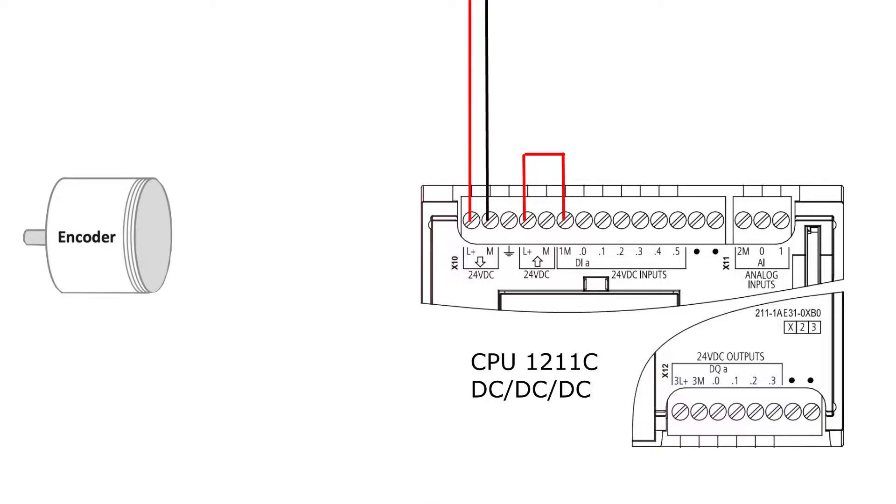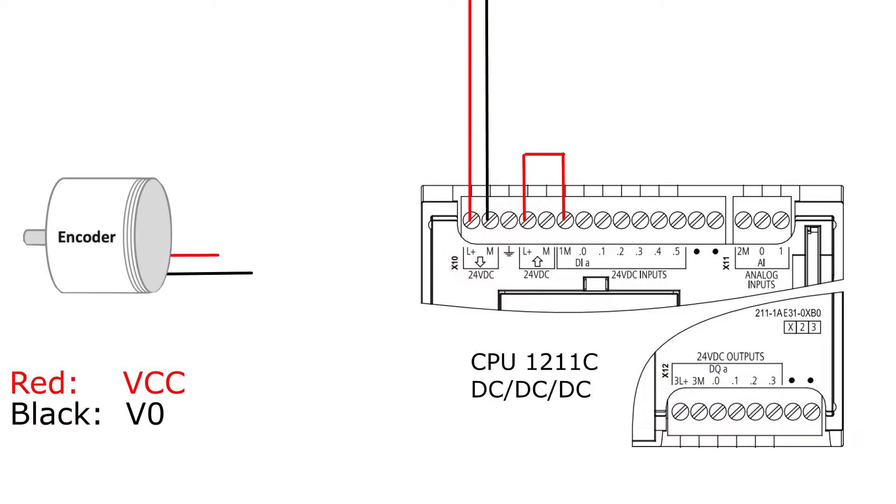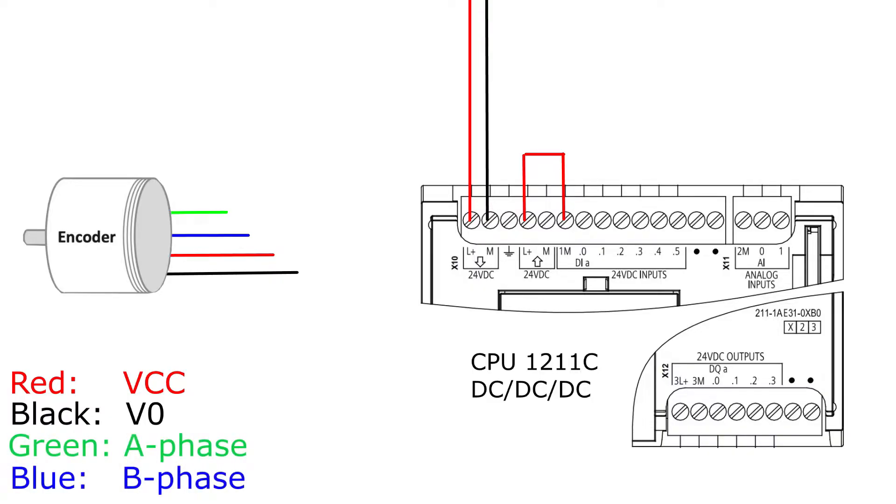From the encoder I am using, there are four wires. Two wires for the 24- and 0-volt DC. Then two wires for the A and B phase. From the red and black cable I want to connect to the PLC's 24- and 0-volt DC output terminal, which will give power to the encoder.